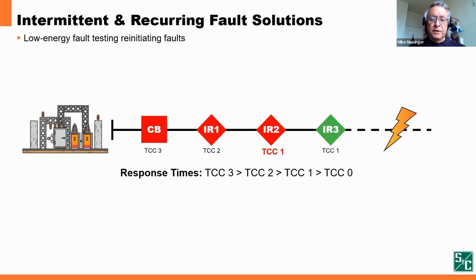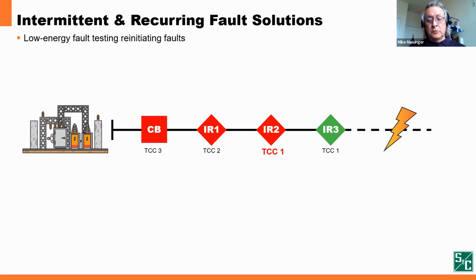After that period, we're going to shift back to the TCC that we started with, TCC 1. Next slide. At this point now, IR3 has been waiting, and we put a hold timer on it to keep it from responding until IR2 shifted back to its normal TCC, TCC1. Next slide. Now IR3 does the same thing that IR2 did. It applies a low energy test. It's not going to detect that tree limb because that tree limb is going to take time to recarbonize. Next slide.